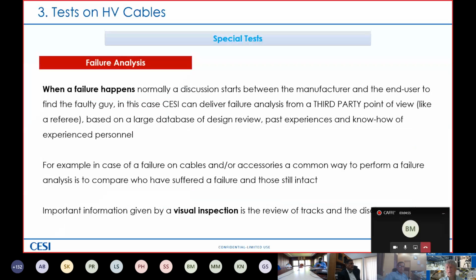Failure analysis. Failure analysis is another, I put it in the section special test, even if it's not a special test, it's a special service, but it's more and more requested by our clients. Why? Because when a failure happens, normally you have a discussion starting between the manufacturer of the cable or of the accessories and the end user to find the guilty guy. Someone says that your design is a very poor and weak design. You are the guilty guy.